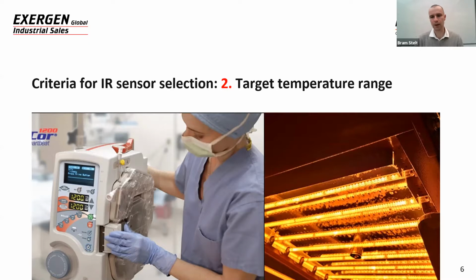So Bob was telling you that various temperature ranges are an important criteria for sensor selection. The medical range is a very small range, maybe from 30 to 50 degrees C, but in drying applications it can go all the way up to 250 C. There might even be applications in the steel industry all the way up to 2000 C. It's a very important criteria to see what is the temperature range of interest. It could be a wide range, but generally there is a smaller range that's really the critical range. So it could be that the customer wants to measure from 0 to 250 C, but that around 170 C, that's the real critical range. That's when, in drying applications for instance, the substrate is really drying.